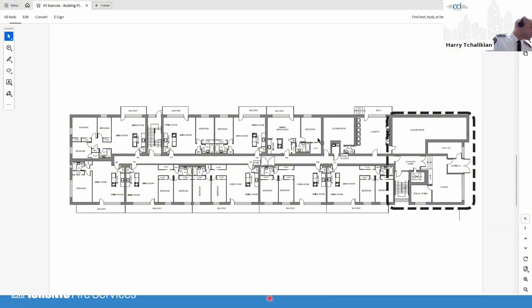Let's look at sentence 3. Where a building contains a storage garage, a carbon monoxide alarm shall be installed, A, adjacent to each sleeping area within each suite of a residential occupancy or care occupancy, where the suite has a common wall or common floor-ceiling assembly with the storage garage; B, on each story within a sleeping area within each suite of a residential occupancy or care occupancy, where the suite has a common wall or common floor-ceiling assembly with the storage garage, and also sleeping rooms that are not dwelling units also need it.